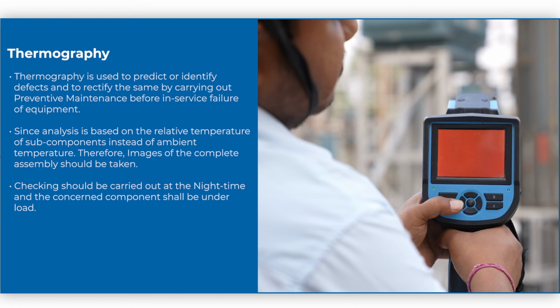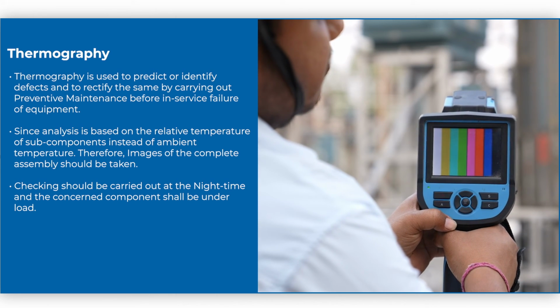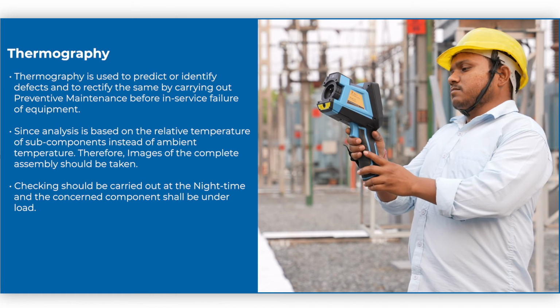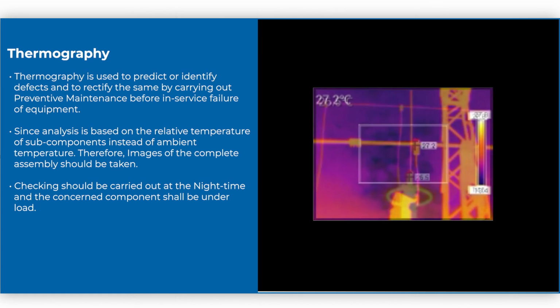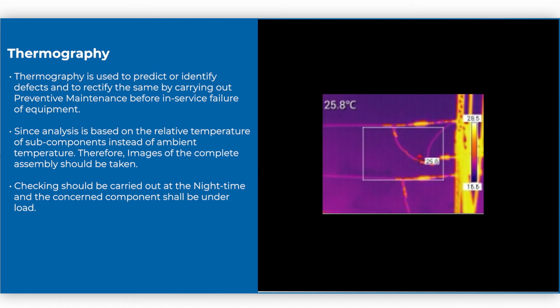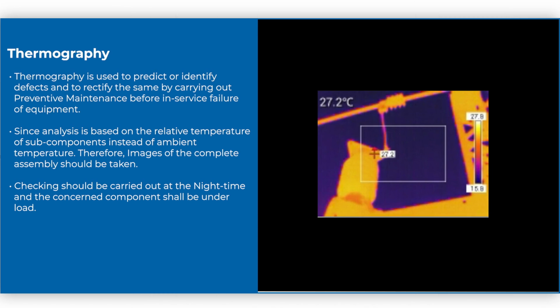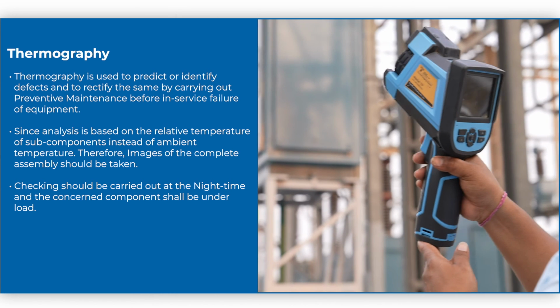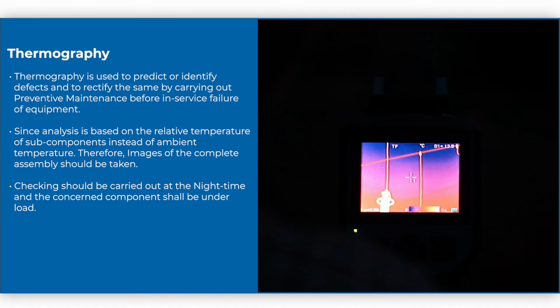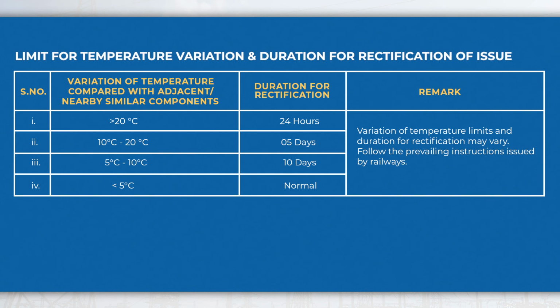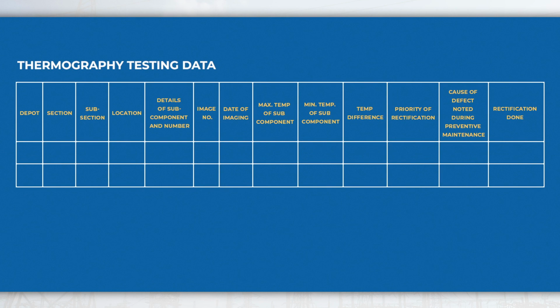Thermography. Thermography is used to predict or identify defects and to rectify the same by carrying out preventive maintenance before in-service failure of equipment. Since analysis is based on the relative temperature of subcomponents instead of ambient temperature, therefore, images of the complete assembly should be taken. Checking should be carried out at the night time, and the concerned component shall be under load. Limit for temperature variation and duration for rectification of issue is given in the table. Testing data may be recorded in this format for further investigation and future reference.